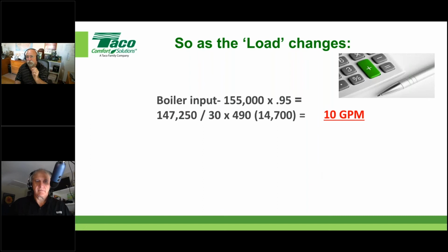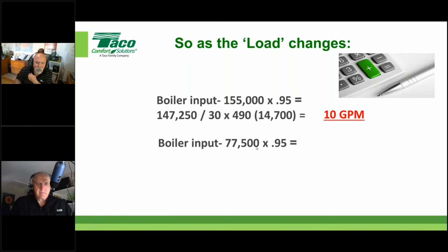Okay, now the thing that changes this would be allowing the boiler manufacturer to control the speed of the circulator. So if you're doing fixed speed circulators and you don't have that external control, I want you to understand this. Here's that same calculation we used at a 30 degree delta T at high efficiency, saying that we needed 10 gallons a minute. What if the load changes to half of that? Here's half a load condition, part load conditions on that system, right?